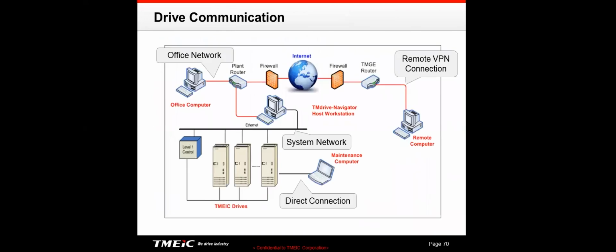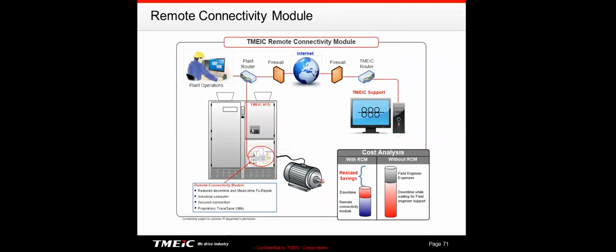Drive control software: we generally control and troubleshoot a medium voltage drive remotely. So you can go back to that Virginia facility, or you can come to our facility in Salt Lake, and we can actually get in. And if you allow us to, of course, that's a firewall issue, we can go in there and program and run the drive and look at the faults and do this remotely, because sometimes when a drive's down, it's really critical.